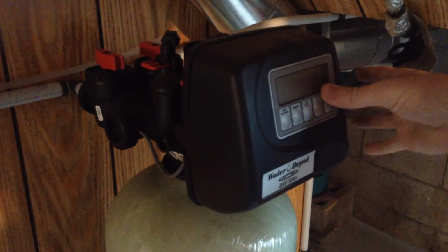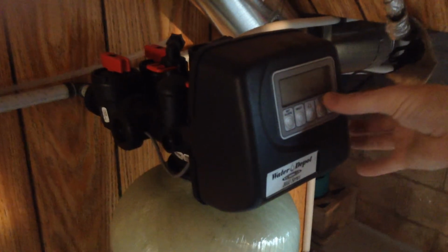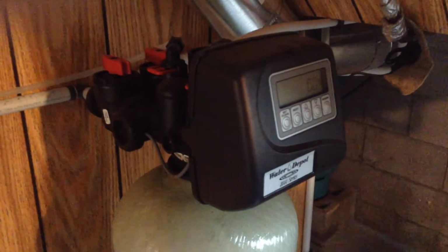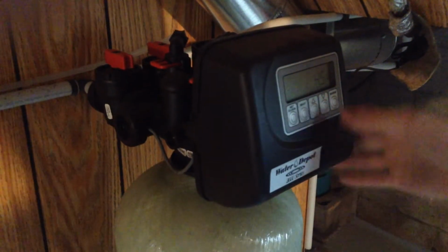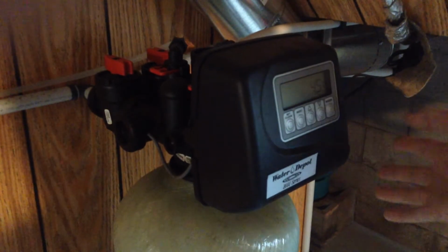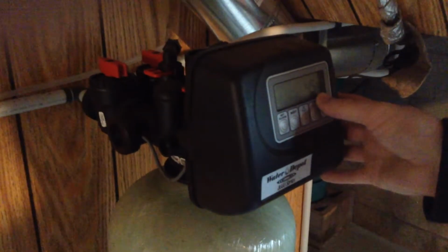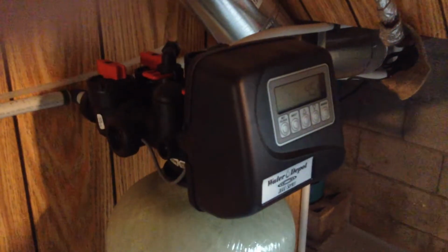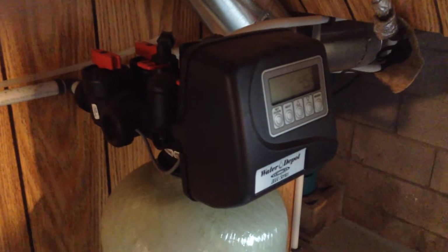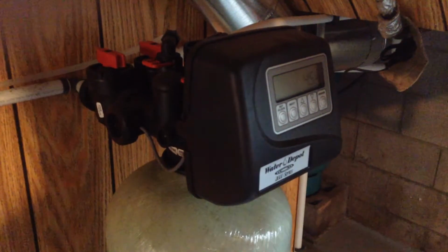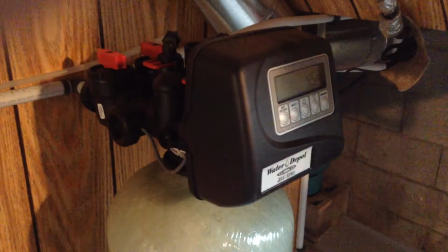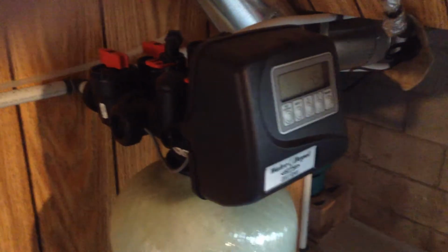Currently, there's 0 gallons per minute flashing, 0.0, so there's no water running. If I turn the water on, it'll tell me the current flow rate. The maximum flow rate ever in the property is 4.5 gallons per minute. It's not a huge number, but it's reasonable for 1-2 taps. Sometimes we'll see up to 7-10 gallons per minute. It depends on how much the pump can service, the flow rate coming from the pump.